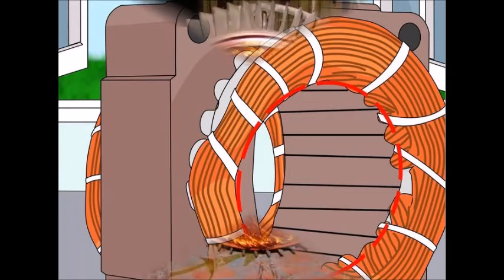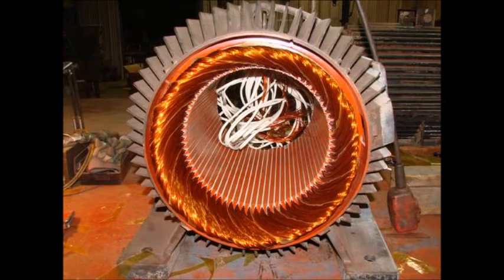Rewind the armature and/or stator using the same gauge and type of magnet wire that was on the original motor. If you're more experienced, you may wish to upgrade your wire's quality, substituting a nylon and polyurethane coated wire for the original enamel coated wire, for instance.